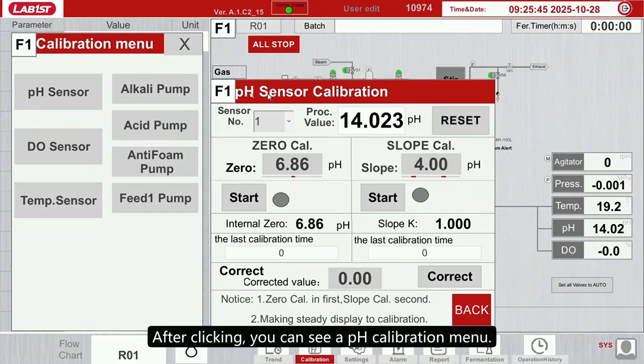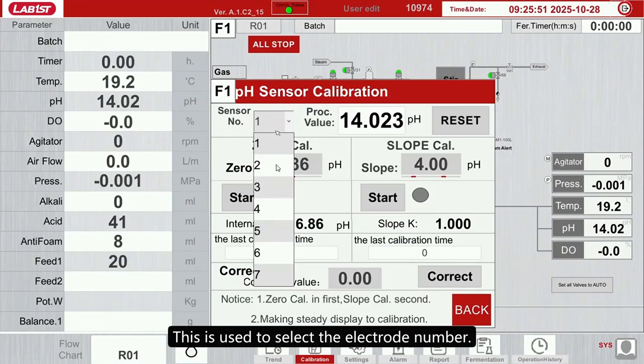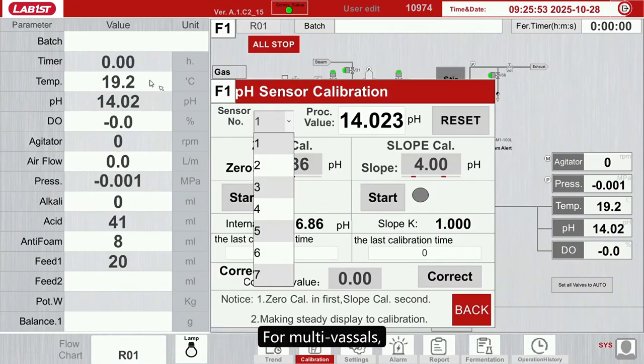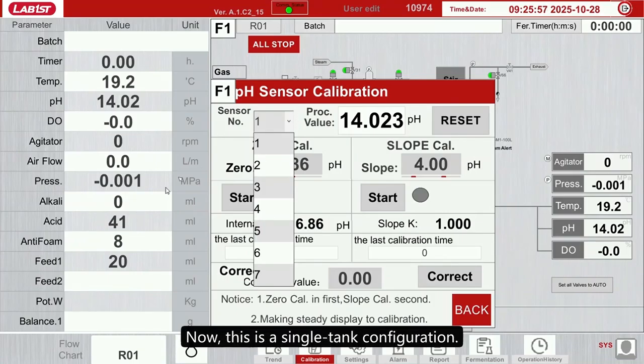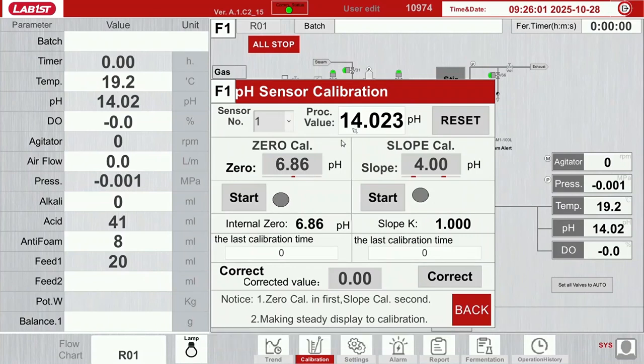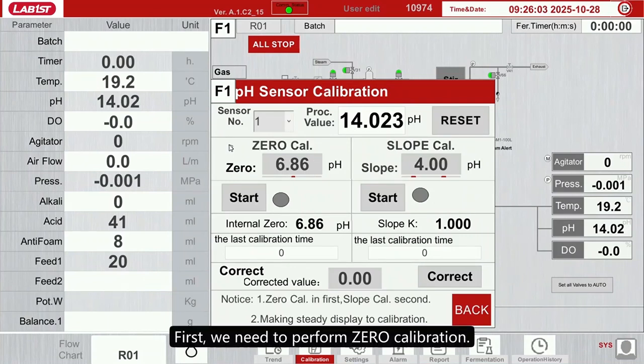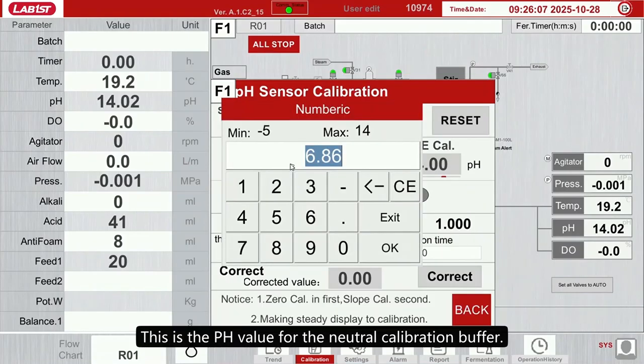After clicking, you can see a pH calibration menu. This is used to select the electrode number. For multivessels, it is more commonly used in such cases. Now, this is a single tank configuration, so generally, choosing one is sufficient. First, we need to perform zero calibration. This is the pH value for the neutral calibration buffer.